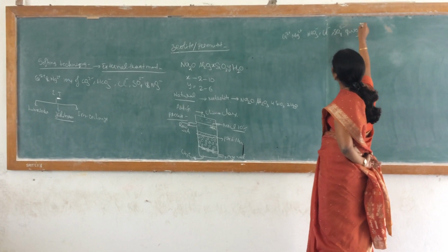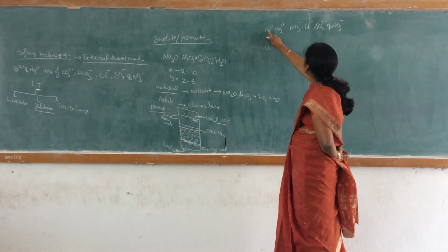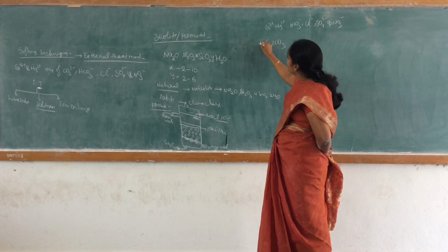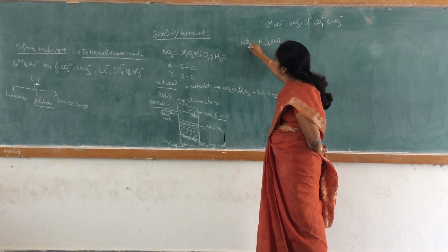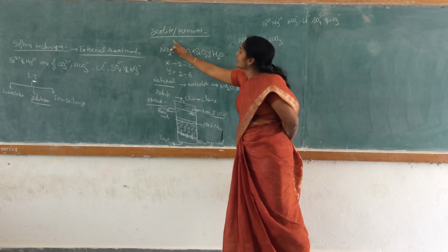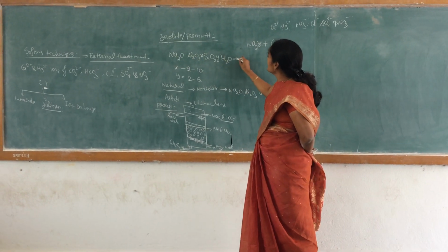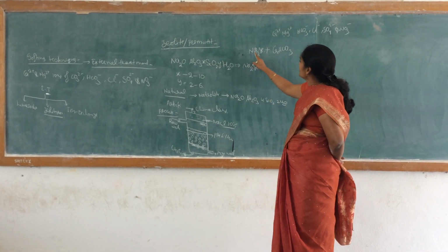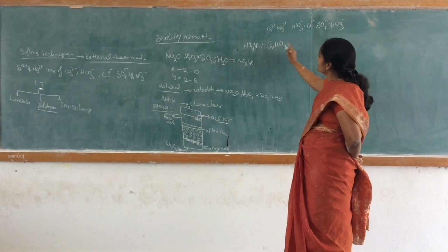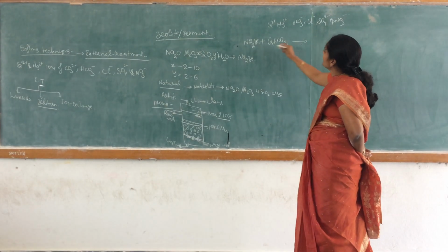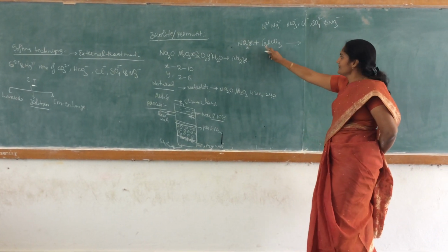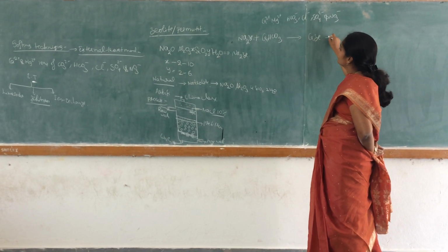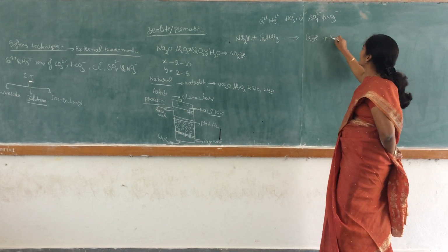First we consider calcium bicarbonate. When it is passed through the zeolite bed, whose formula is written as Na2Z, the sodium zeolite exchanges its sodium ions with the calcium, producing calcium zeolite and sodium bicarbonate.